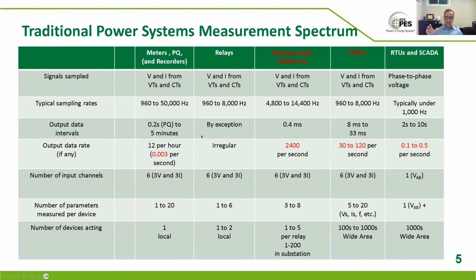But that's a different layer. In the measurement domain, both are important. So between high voltage and low voltage, where the electronics can help, there is the instrument transformer. In a way, that is a filter that blocks some information. And then there is the device that does the sampling, and if it's slow or if it doesn't do the job right, that's another filter that can result in loss of information.